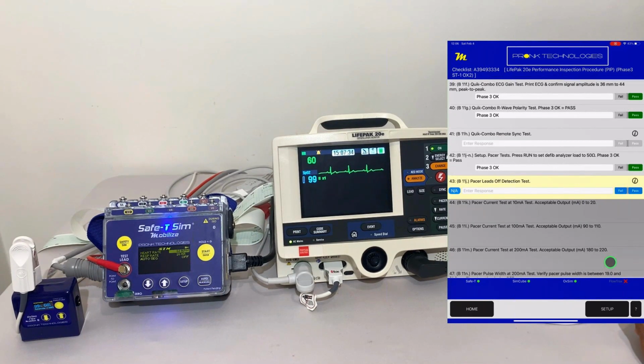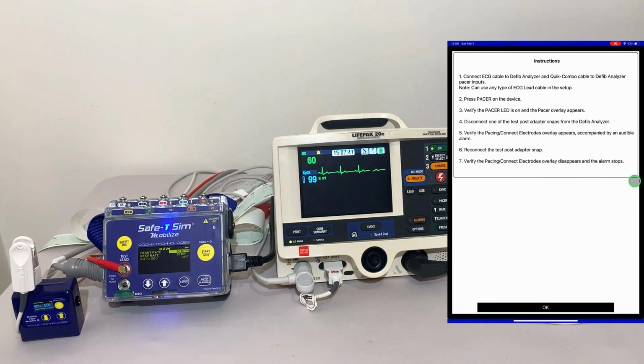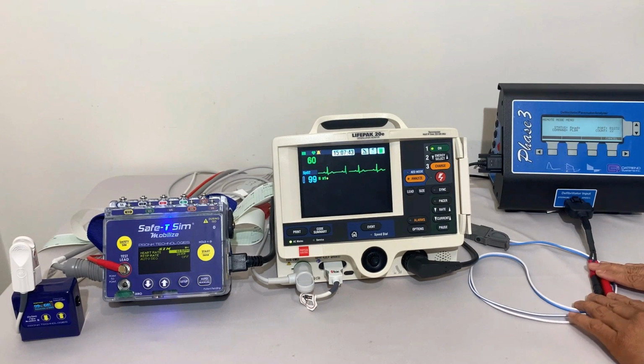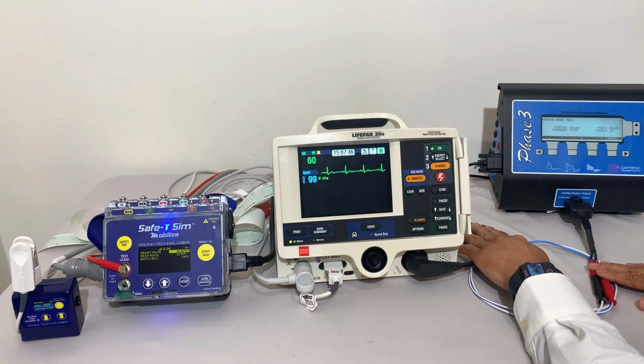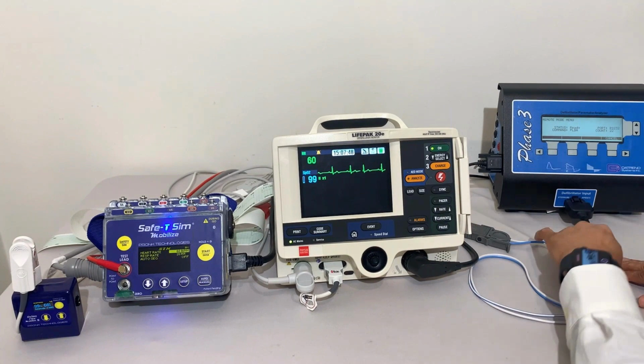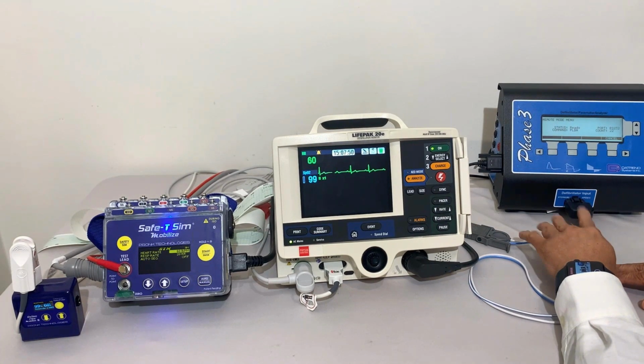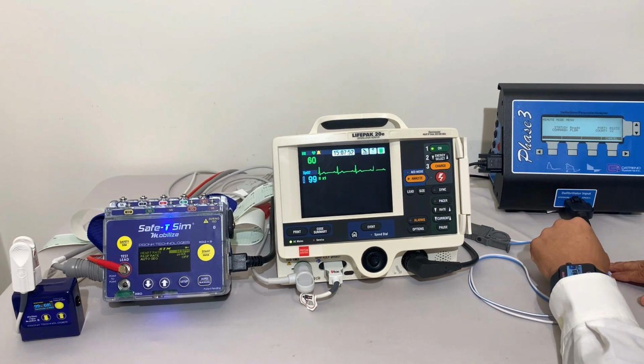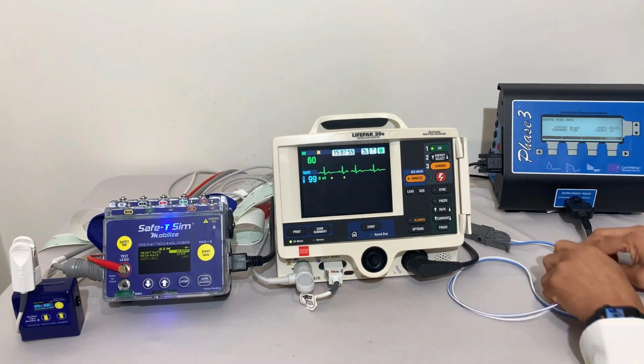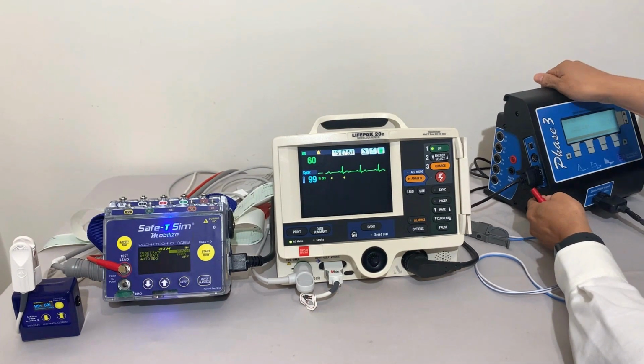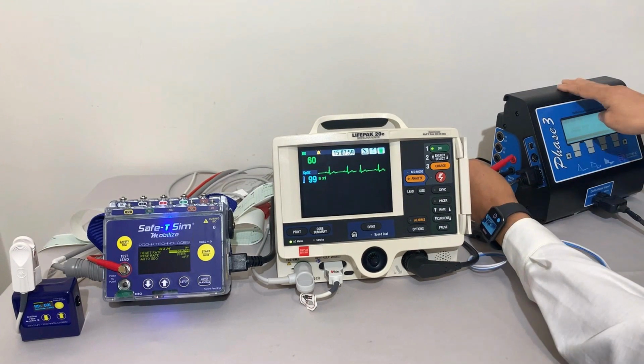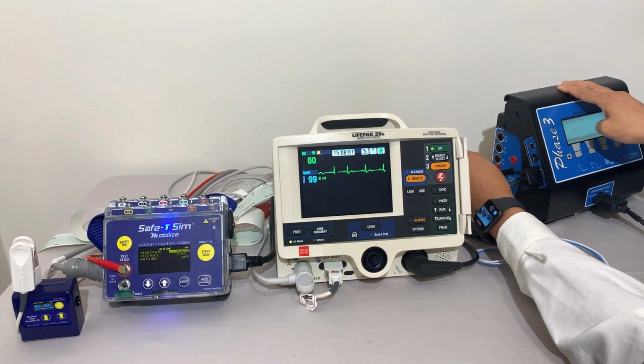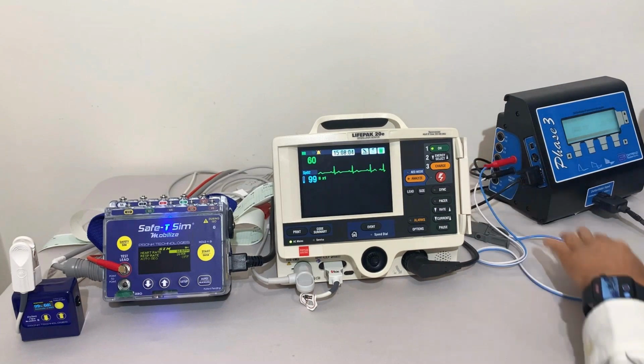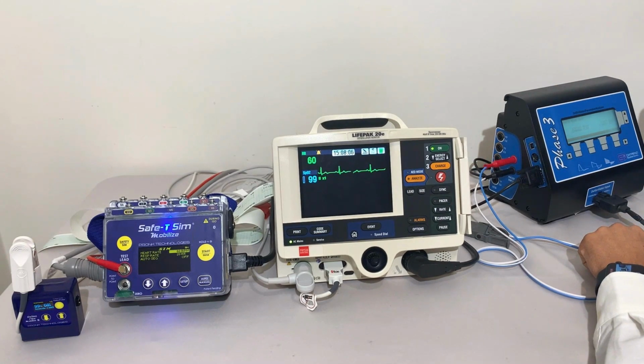And the next test is we need to do a pacer leads off detection test. There are some things we need to do in the setup to make sure we have that configured properly. And one of the things we need to do is move the quick combo cable connections from the defibrillator input port, which is what we use to do discharge or shock testing, over to the pacer ports. So we would disconnect it from here, and I'll turn the analyzer around so you can kind of see it here, and we connect it to the ports that correspond to the pacer here on the left. So that allows us to be ready to do the pacer testing.